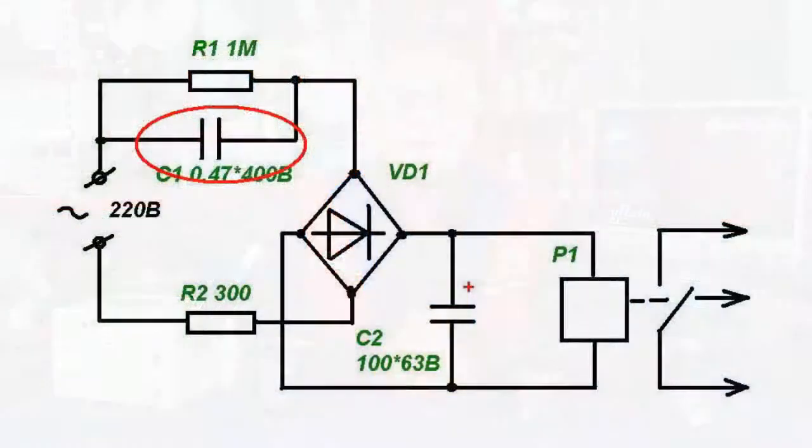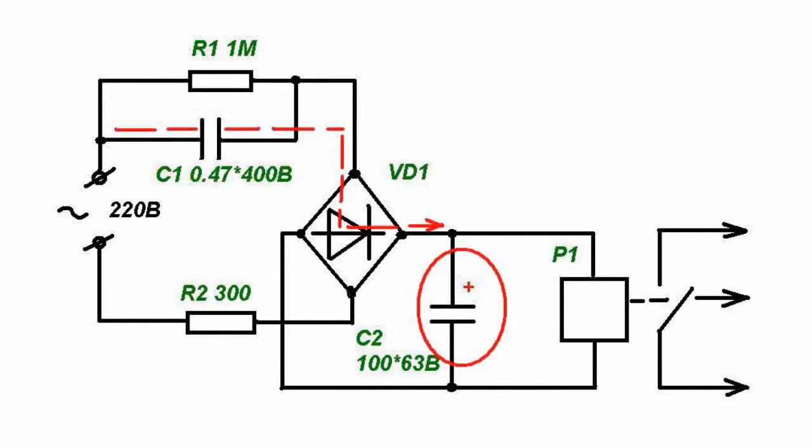The operation principle of the device is the following. If power supply is available, voltage from the network enters the rectifier bridge through quenching capacitor C1. Then constant voltage feeding relay winding P1 is generated by capacitor C2. In this case, the relay contacts are switched to the main supply.